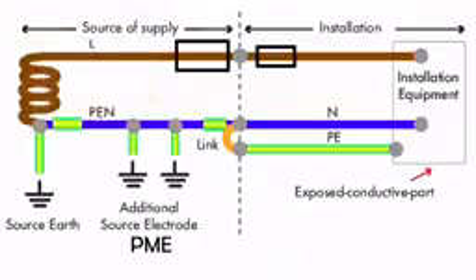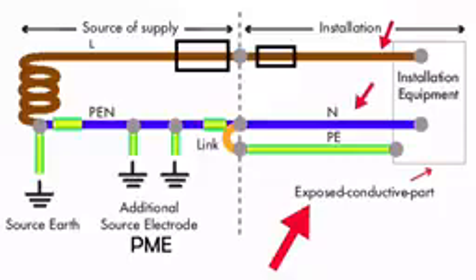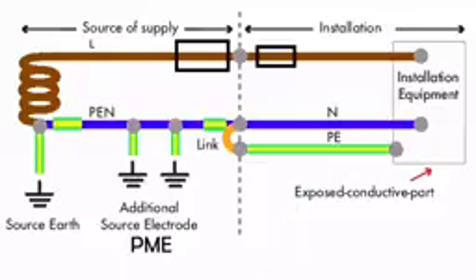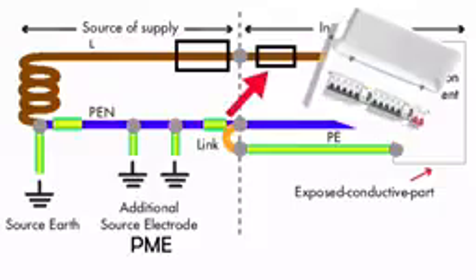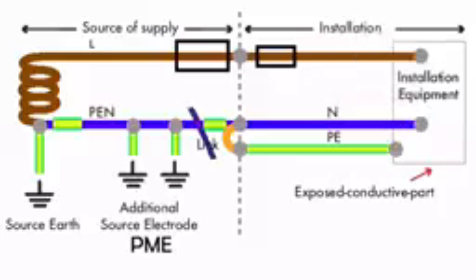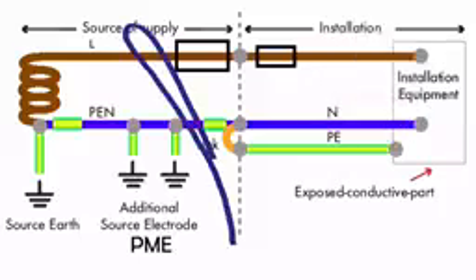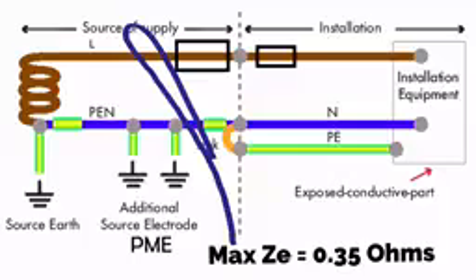The installation shown on the right hand side can be a lot shorter in length than that of the supply authority's cable, comprising of a line, neutral and circuit protective conductor. The neutral and earth are only combined on the supply authority side and not within the installation. The fuse for this circuit will not be 100 amps, considerably less, maybe 20 amps, and housed within the consumer's unit. The maximum external earth fault loop impedance for a TNCS earthing arrangement is 0.35 ohms.